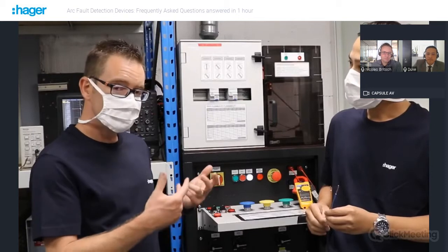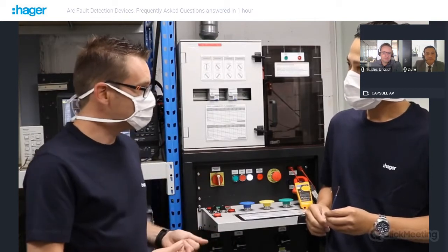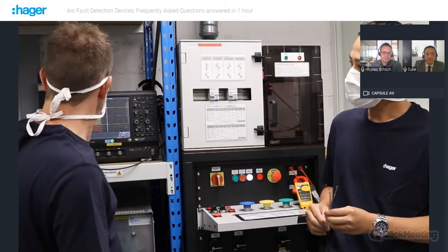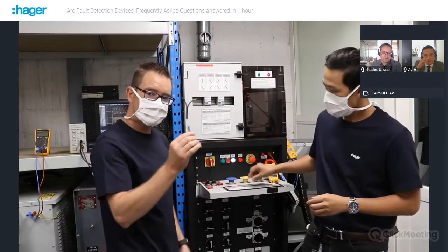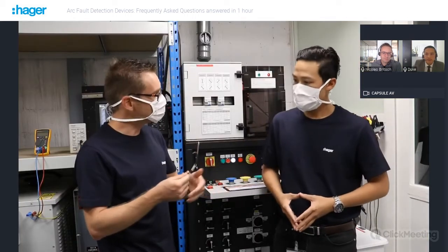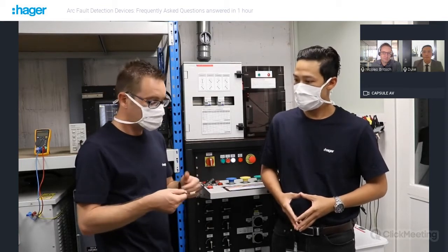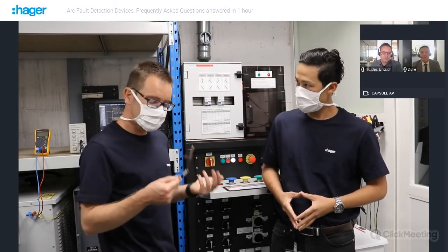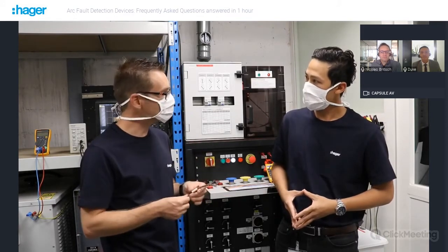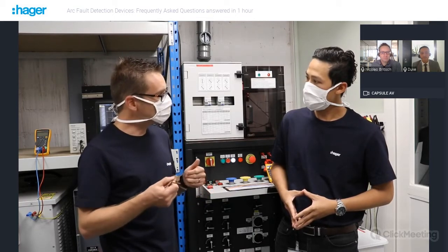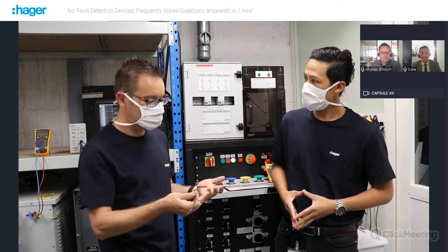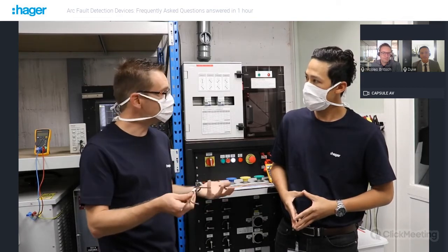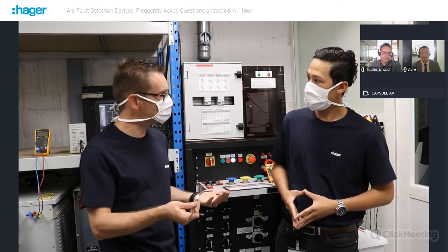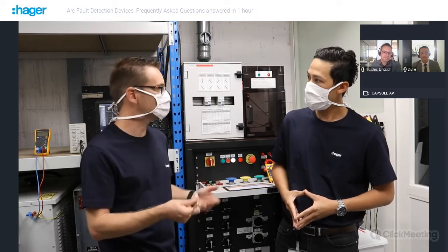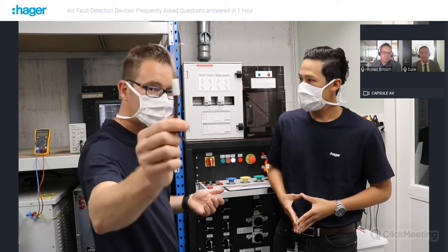That's why we have to use a specific piece of cable which is prepared in a way to be sure that you have enough energy. This piece of wire has been prepared according to the standard. In the standard for AFDDs, EN 62606, there is the description of how you have to prepare this piece of cable in order to be sure that you will have enough energy in the fault to start a fire. And in this case, the AFDD will have to detect this fault and to trip in order to protect the circuit. So let's test this piece of wire and see what happens.